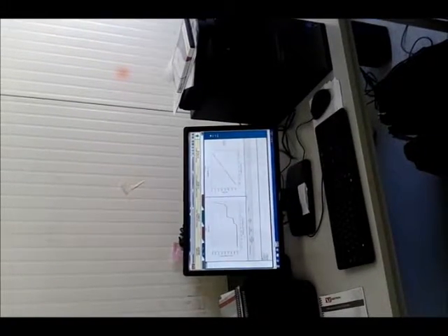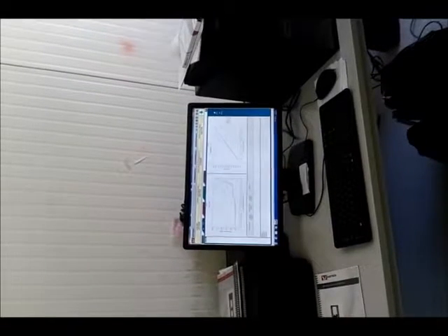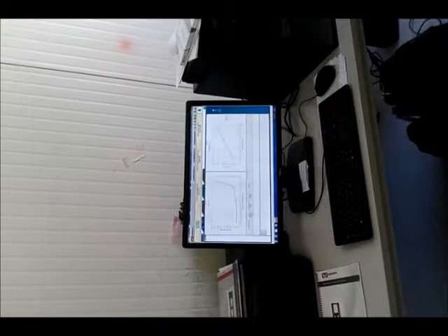The only one problem we have at the moment is that the power here is not perfectly stable. There is a fluctuation on the power. We have an uninterruptible power supply on the computer, which is fine. We need a larger one for the machine, because if you get too big a fluctuation, you can lose the communication. If that happens during a test, you lose the data. So the customer is looking to get a UPS that will be suitable for this machine, which will resolve that issue.